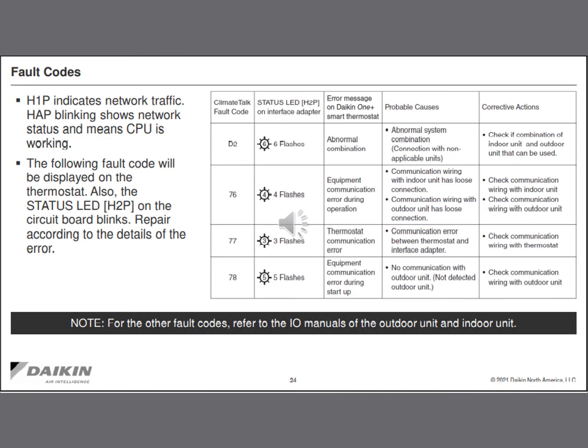Also on the D24V Gateway adapter are a couple of LED indicator lights, and they are H1P and HAP as well. The H1P typically indicates network traffic. The HAP blinking shows your network status and shows you that your processing unit is functioning the way it should. We also have the H2P on the circuit board, and the number of flashes on that H2P will indicate an error. Usually these are communication errors or errors with the thermostat. There's a handy chart there that will show you what these errors are.